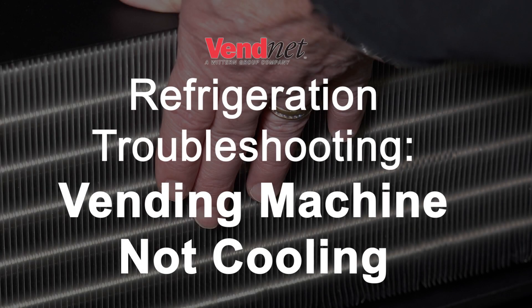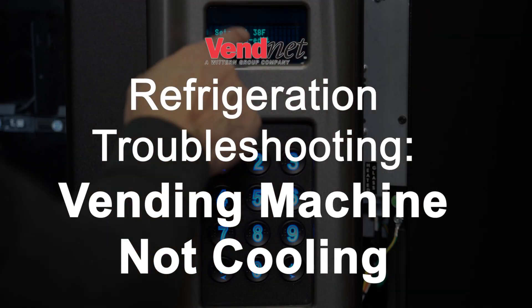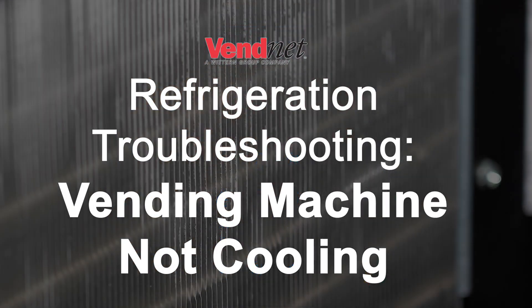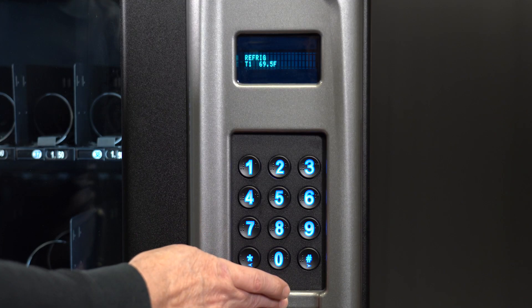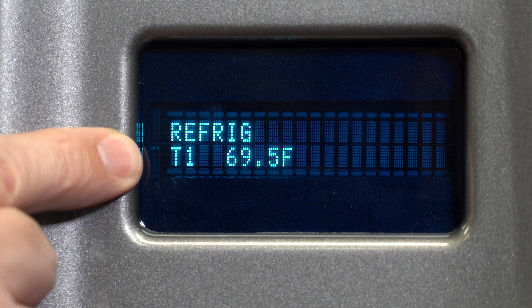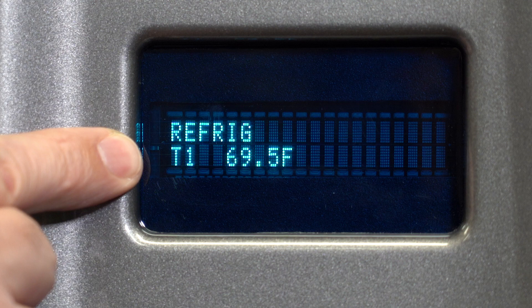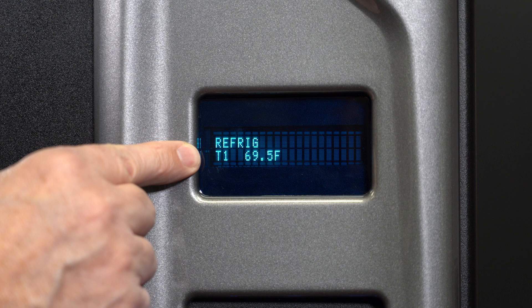If you are having an issue with your machine not cooling, begin troubleshooting by checking the temperature of the machine. Push zero on the keypad. If you see a star when the temperature is displayed, it indicates that the control board is calling for the refrigeration system to come on.